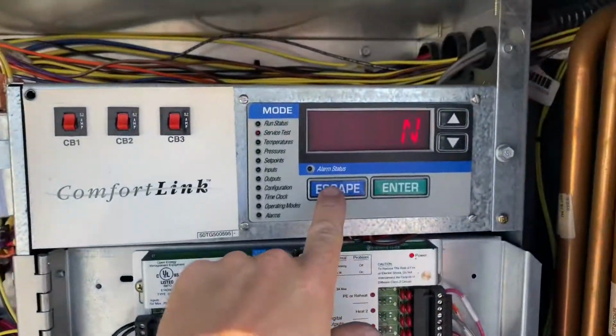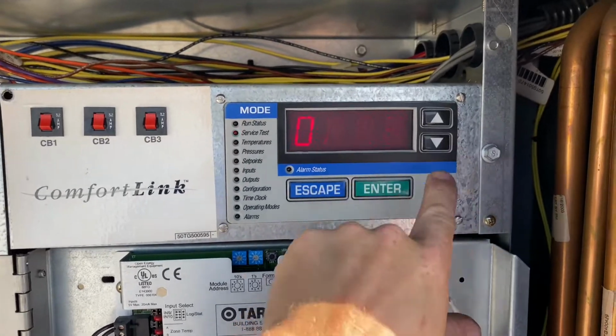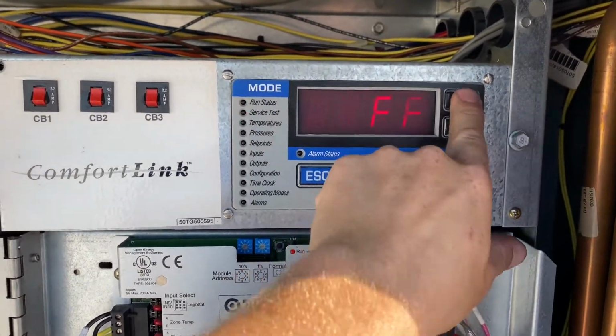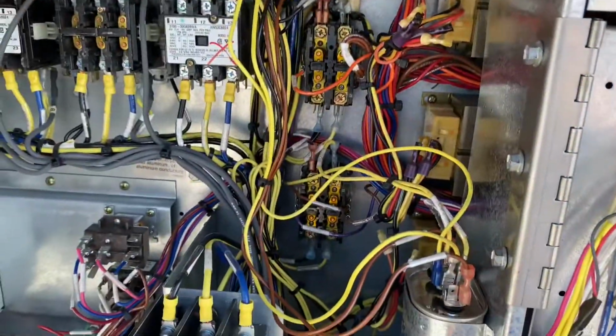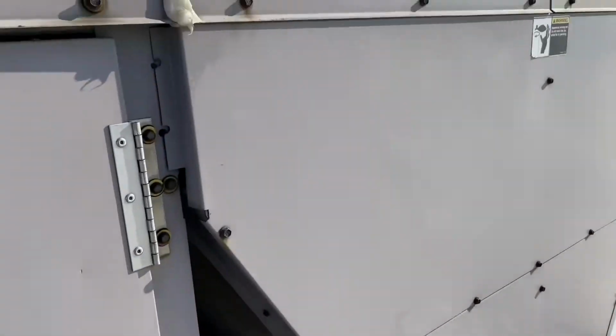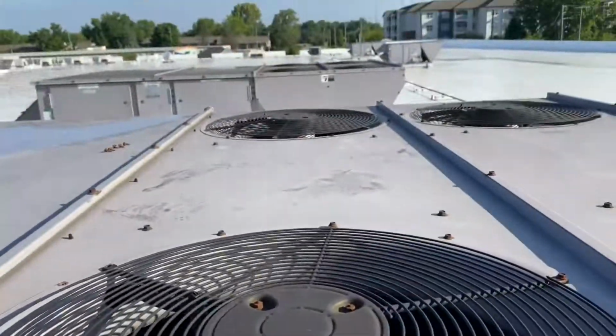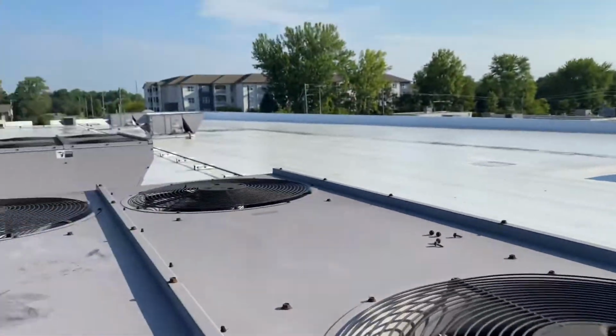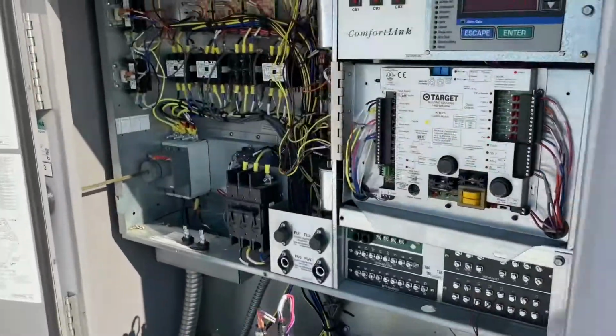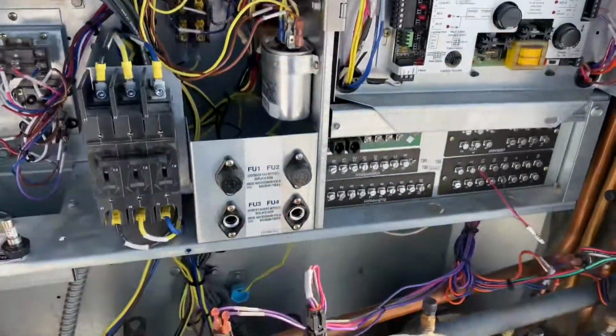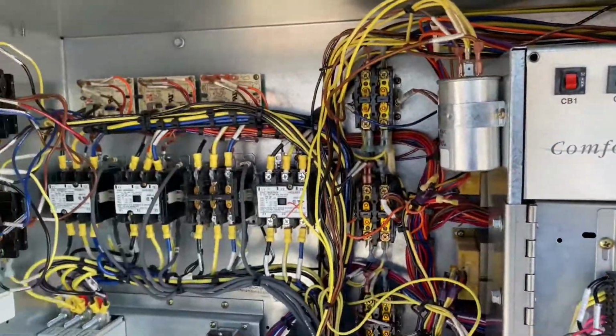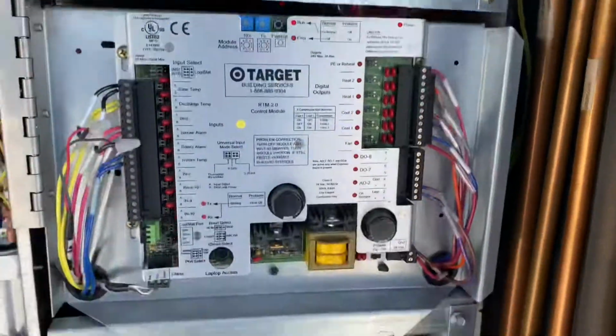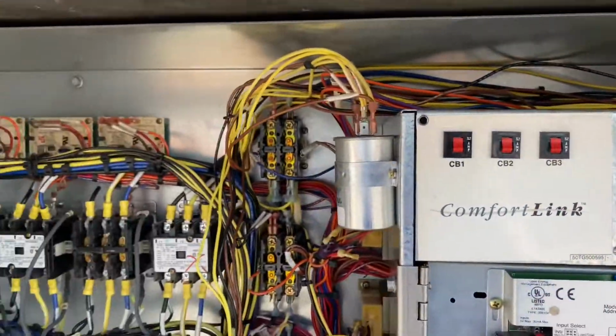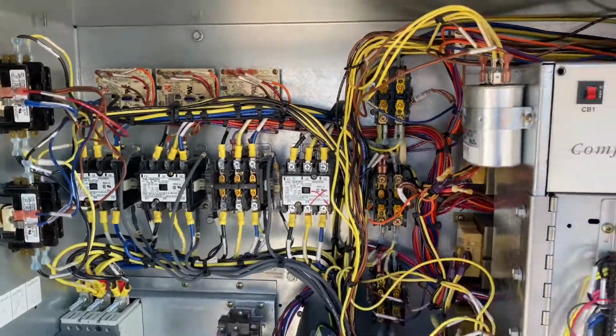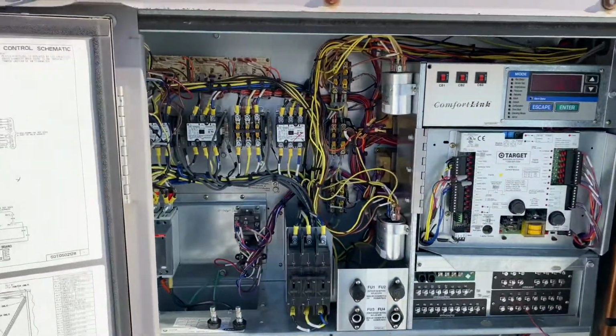Come back over here, escape out, go up to, or down to 3. On. That contactor pulled in and is running this fan. So I now have 2 fans running. Still running, not popping any fuses. Contactor pulled in, still power going to the board, power going to the communications. So that tells me I will be replacing fan number 1 and fan number 3 today.